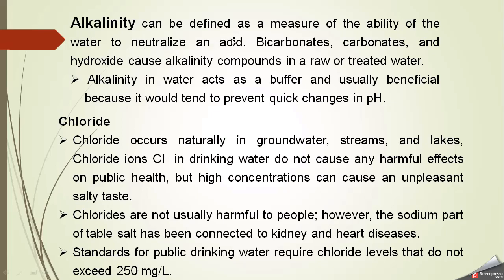Alkalinity is a measure of the ability of water to neutralize an acid. It is due to bicarbonates, carbonates, and hydroxide compounds present in water. Alkalinity acts as a buffer and is usually beneficial because it prevents quick changes in pH. However, excessive alkalinity and very low alkalinity are not good for water systems, so balance is needed and guidelines must be followed.